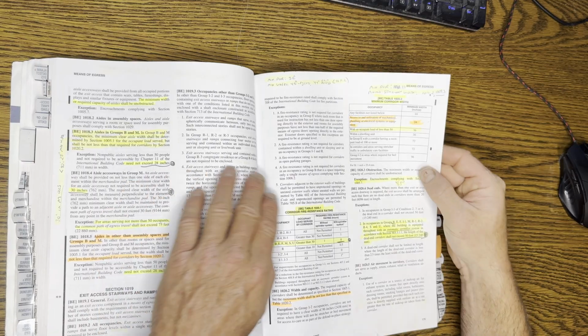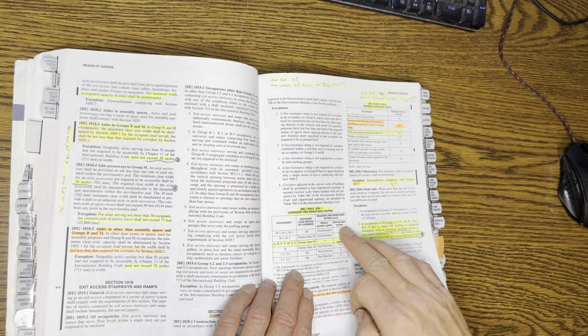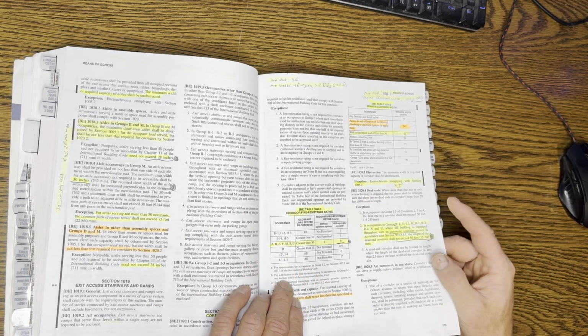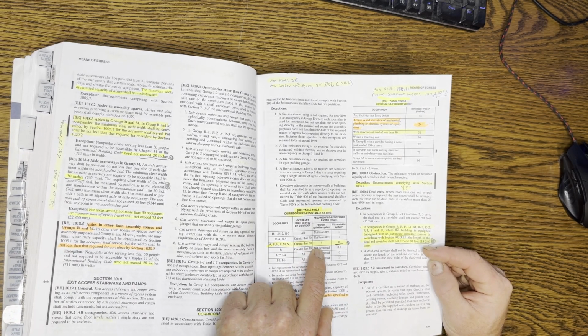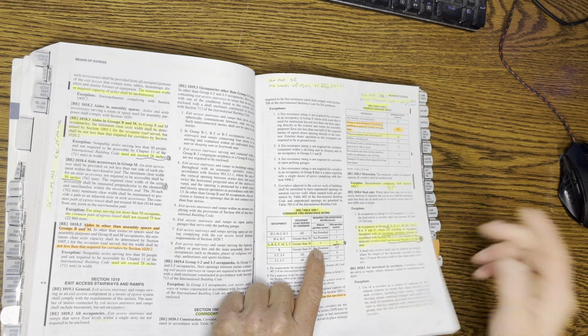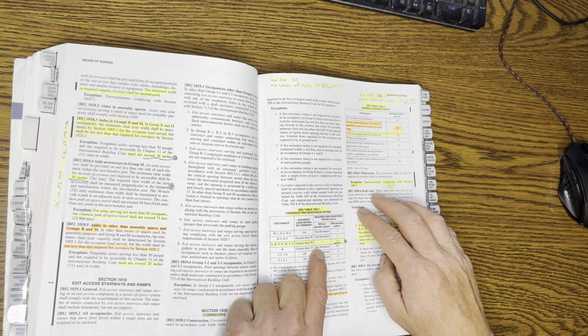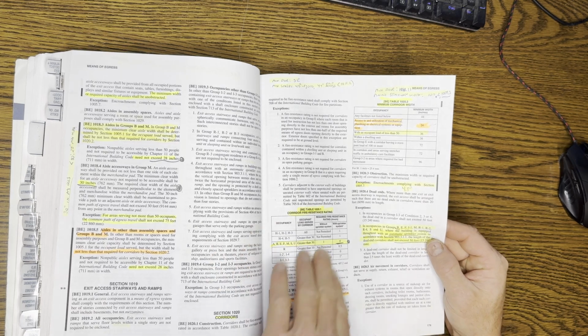Okay, so over here, let's take a look at this so you can understand it. Required fire resistance rating. If you have suppression, a lot of stuff goes away. But typically, let's just target a B occupancy really quick. If you are in a B occupancy, you have to have 1-hour corridor rated barriers if you are not suppressed and you're serving more than 30 people. That's how you read that table.